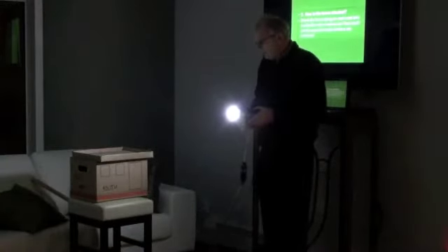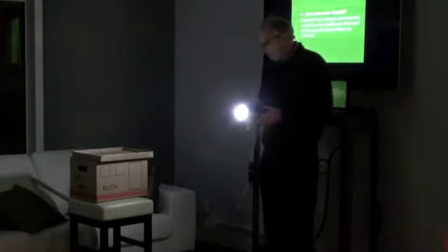People will actually put aluminum foil on the window to try to stay comfortable without running a lot of air conditioning. And every patio door that you have facing west, if you want to stay comfortable, you have to put a 5,000 BTU per hour air conditioner to handle that cooling load.